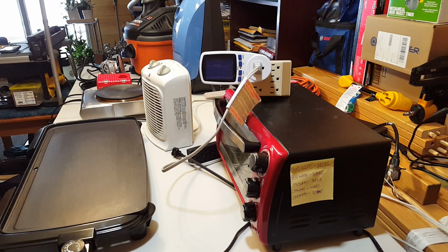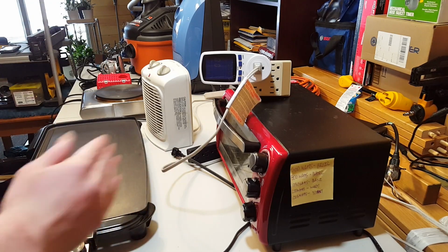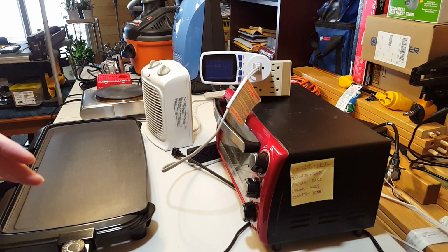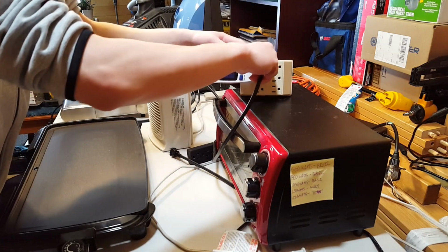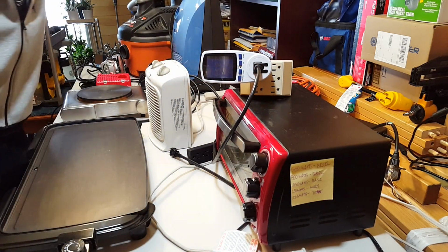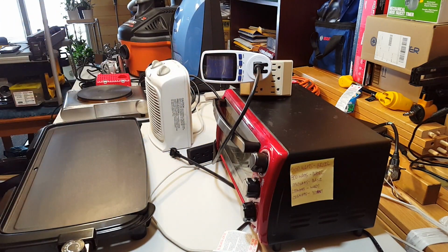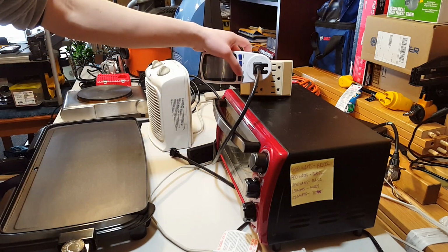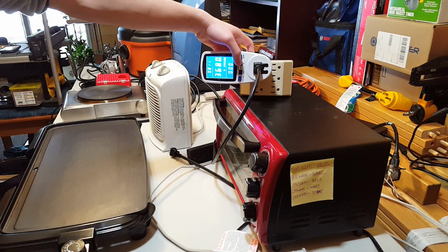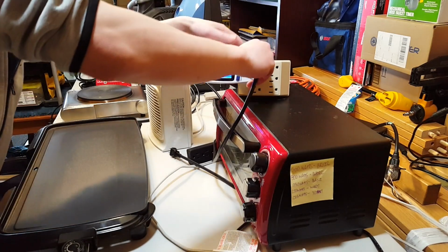The next thing we'll do is surge testing. Let's try all the motors first, and then we'll have a bunch of space heaters on at the same time, and then we'll do surge testing with a motor and see if that will overload the BMS into overcurrent. So let's do the shop vac. Okay, so it was able to start that no problem, but we will also be measuring the surge amps as well as running amps. This is on watts.